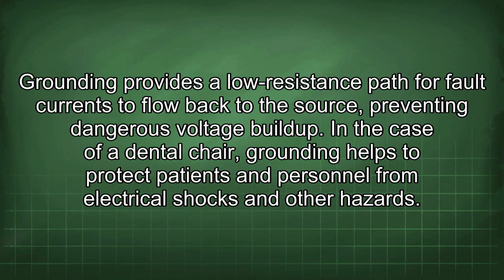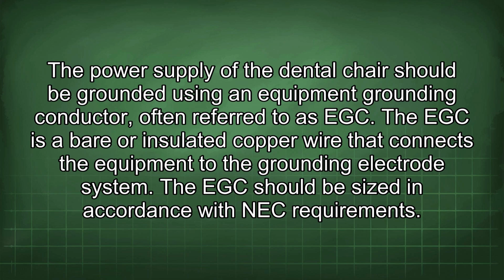Grounding provides a lower resistance path for fault currents to flow back to the source, preventing dangerous voltage buildup. In the case of a dental chair, grounding helps to protect patients and personnel from electrical shocks and other hazards. The power supply of the dental chair should be grounded using an equipment grounding conductor, often referred to as EGC. The EGC is a bare or insulated copper wire that connects the equipment to the grounding electrode system. The EGC should be sized in accordance with NEC requirements.